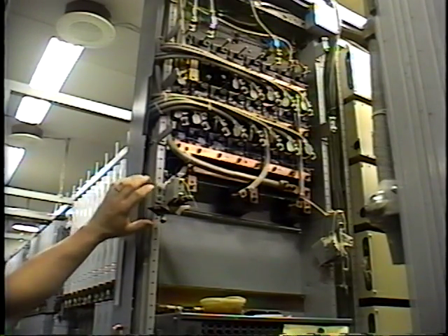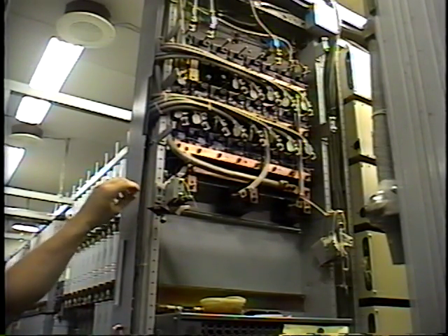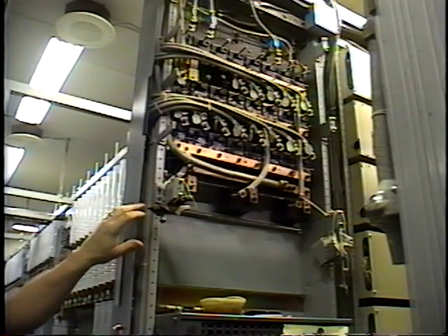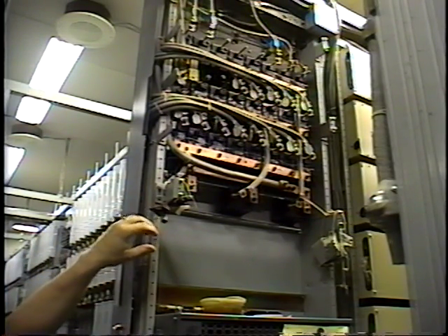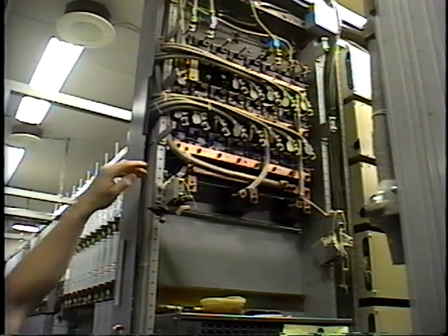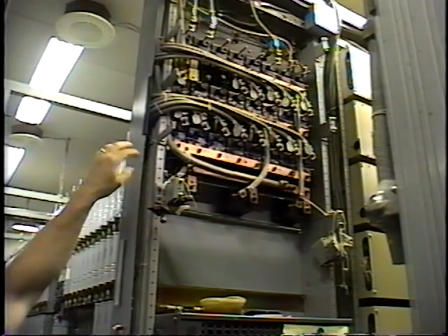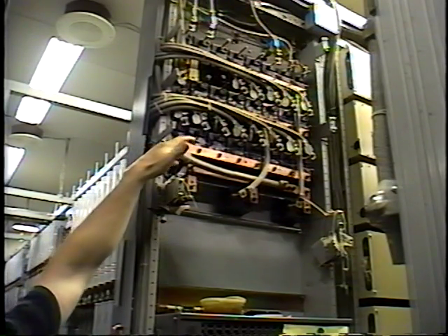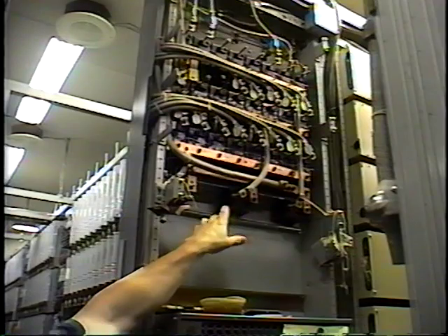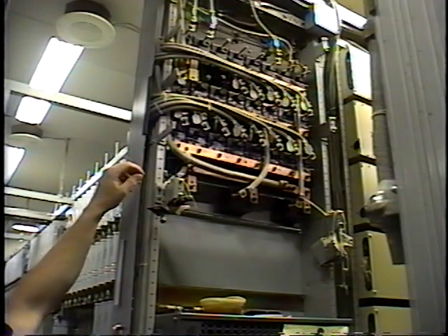Currently we're looking at the power distribution for the central office, because I have one single 100 amp rectifier running the entire building. I have that fed through the XY power distribution board with an ammeter and fusing, and then it comes over to the bottom panel here, which then fuses the individual panels.